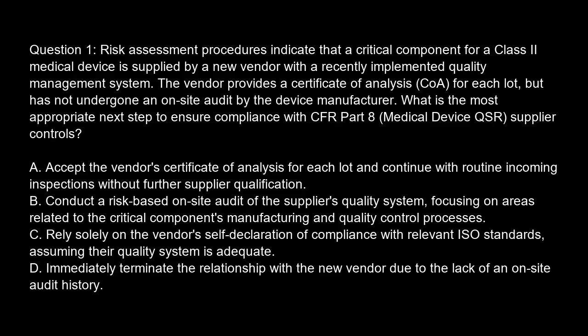Question 1. Risk assessment procedures indicate that a critical component for a Class II medical device is supplied by a new vendor with a recently implemented quality management system. The vendor provides a certificate of analysis, COA, for each lot, but has not undergone an on-site audit by the device manufacturer.